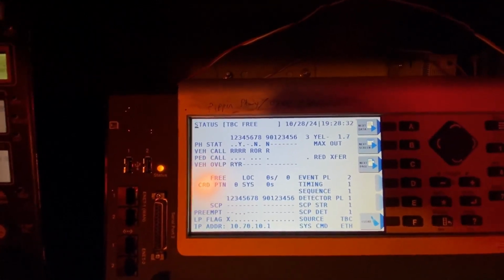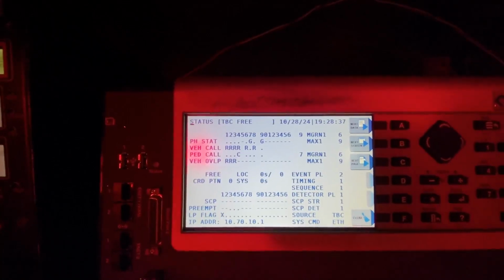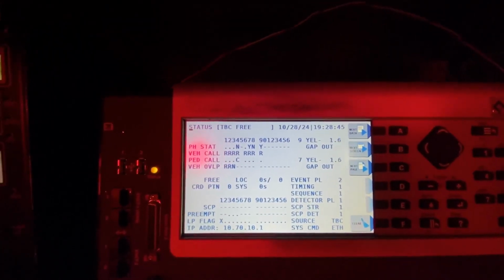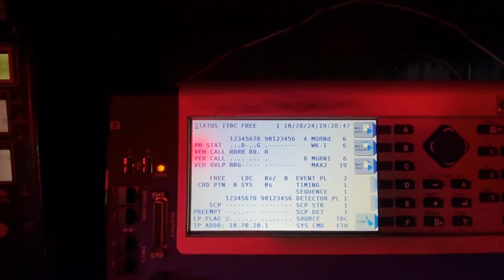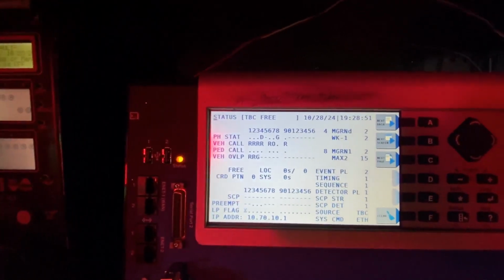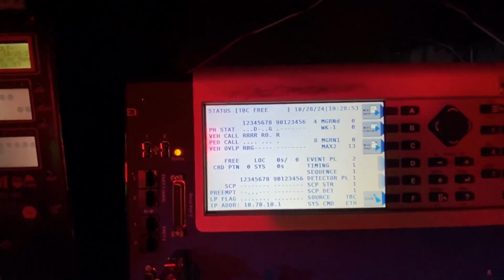So it always calls up 7 and 9, even without the ped phase, so it can just run them together because they're in the same ring and barrier. So I just threw the recall on it to keep things moving, so I don't always have to press the button. And then the logic statement always brings up the ped sign coming out of phase 9.